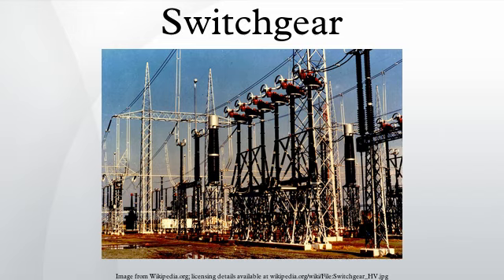In an electric power system, switchgear is the combination of electrical disconnect switches, fuses or circuit breakers used to control, protect and isolate electrical equipment. Switchgear is used both to de-energize equipment to allow work to be done and to clear faults downstream. This type of equipment is directly linked to the reliability of the electricity supply.